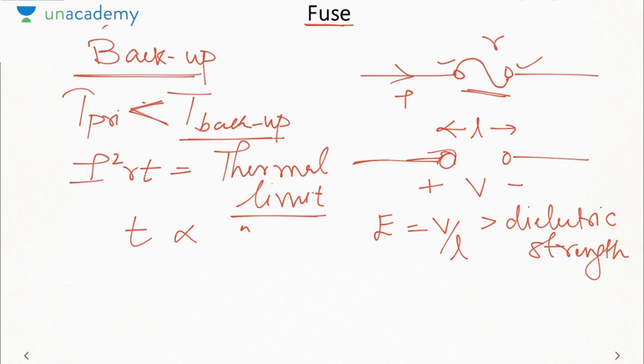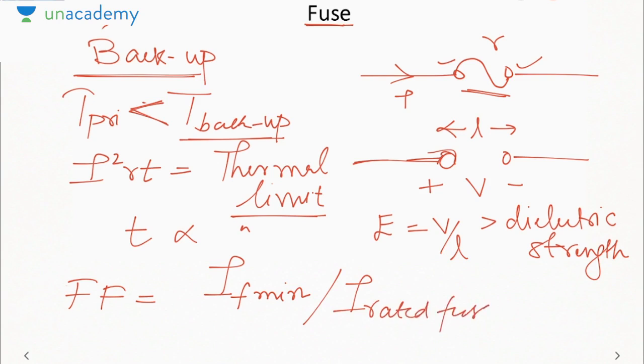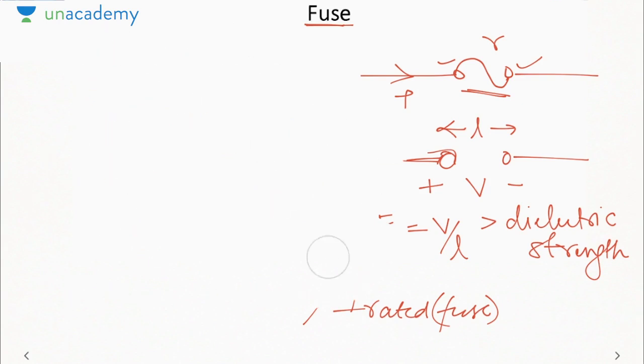Now we define something called a fusing factor. FF means fusing factor, not the form factor. It represents the minimum fusing current divided by I rated of the fuse. Okay. Now what is meant by minimum fusing current? Remember, it is not the minimum fault current, it is the minimum fusing current. Minimum fusing current is the minimum current at which the fuse will operate.